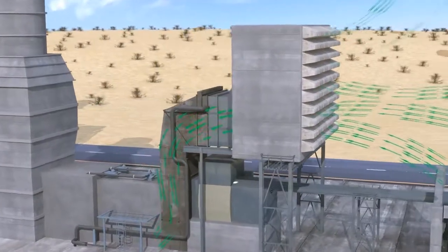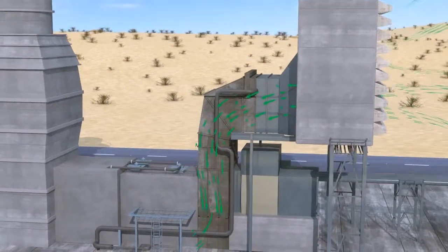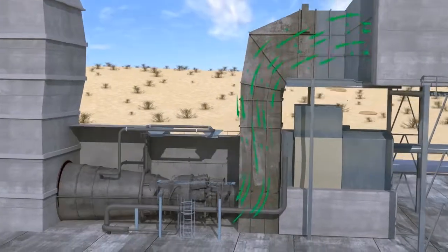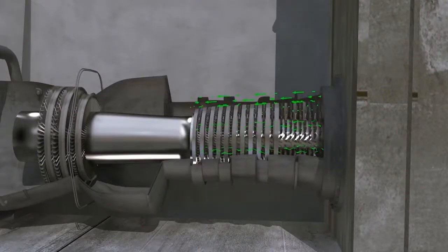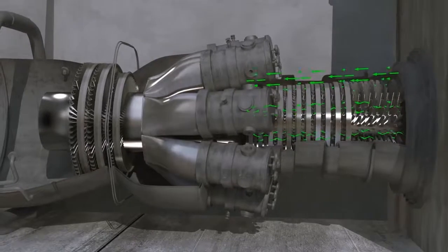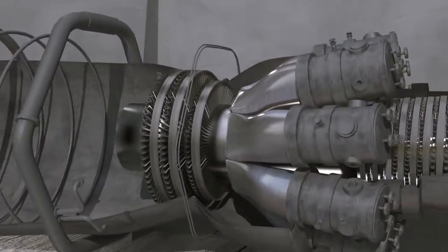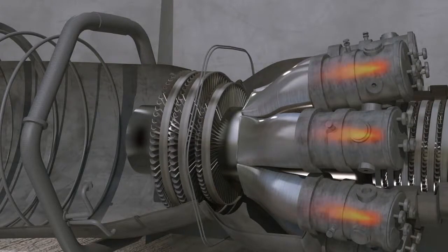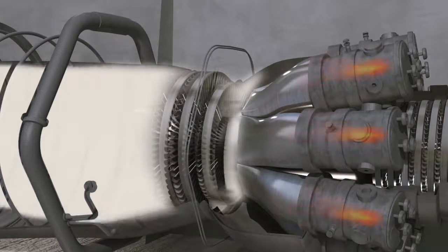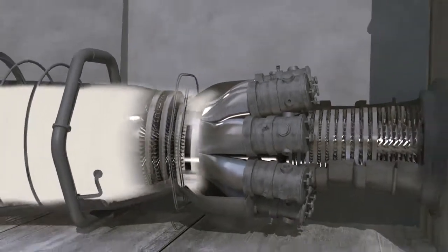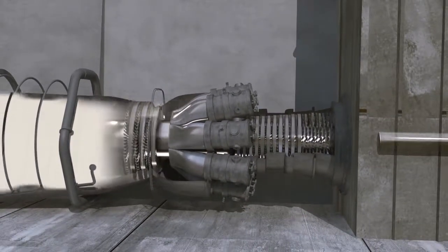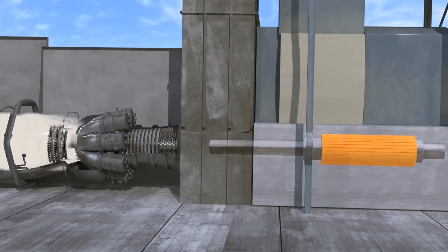In gas turbine, fresh atmospheric air flows through a compressor that brings it to higher pressure. Heat is then added by spraying fuel into the air and igniting it so the combustion generates a high-temperature flow. This high-temperature high-pressure gas enters a turbine, where it expands down to the exhaust pressure, producing a shaft work output in the process. The turbine shaft work is used to drive the compressor and the electric generator that are coupled to the shaft.